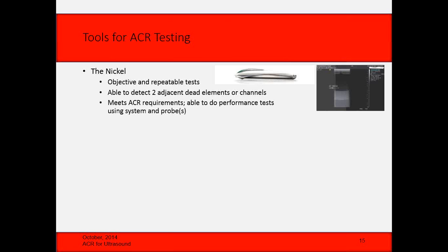It meets the ACR requirements because it does performance tests using the system and probes, and that image there is a picture that shows the injected signals from the nickel. So when you use the nickel, you place it on the membrane of the transducer and you press the switch to turn it on, and it starts listening for transmitted pulses. And when it detects a transmitted pulse, it turns the LED green to tell you that the element and the transmit channel are good. When that happens, it also starts a timer that injects 3 different frequencies, a burst of sound energy, into the nickel at 10 megahertz, 5 megahertz, and 2 megahertz, and then that gets displayed on the screen. So now you've got the nickel injecting a known value into the system, and you can now turn the gain down to where one of those bands of signals just fades into the darkness, and that's your sensitivity test.